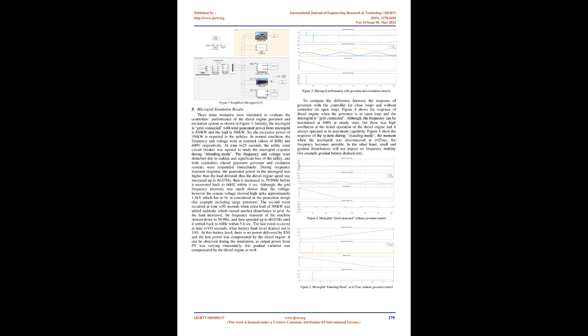[1], [3]. Besides that, the reliability of renewables can be enhanced with advanced power electronics, such as converters and compensators, to maintain grid synchronism at nominal frequency and voltage, even with the variations of wind and sunlight. [1], [4]. To improve the smoothness of power flow and grid stability during load and generation disturbances, an energy storage system, ESS, can guarantee uninterrupted power supply, UPS, with the aid of power electronics.